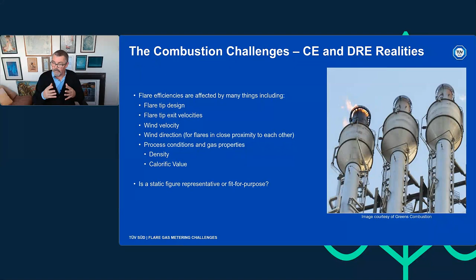The wind velocity is very important. And for example, offshore, when all the flares are very close together, even the wind direction can play a part in the efficiency of a flare, because the flame from one is literally blowing into the gas coming out of another. So wind speed and wind direction play a part. Clearly, the process conditions and the gas properties, in particular the calorific value or the density of the gas. And so the question for industry, I believe, is: is a static figure representative or fit for purpose when it comes to reporting and then trying to reduce emissions? Well, for me, again, the answer is no. A static figure is not fit for purpose, and it's quite easy to demonstrate that.